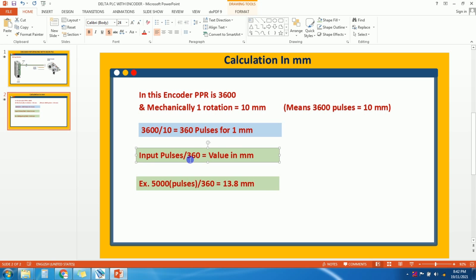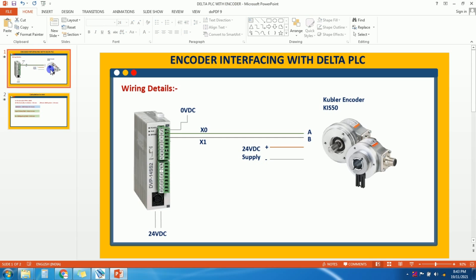Now we will see how to calculate actual millimeters based on input pulses. The formula is: input pulses divided by 360 (pulses per 1mm) gives the actual travel distance in mm. For example, if we have 5000 pulses at input, divided by 360, it means 13.8mm travel distance. Let's start the programming part — open WPLSoft, which is for Delta PLC programming.